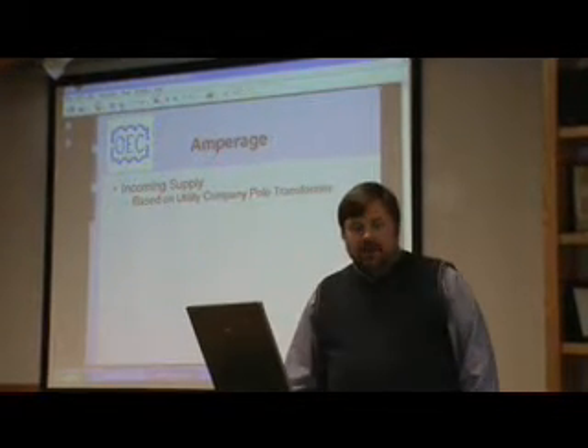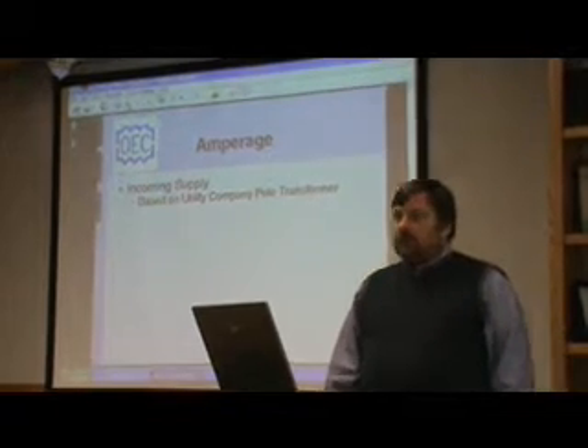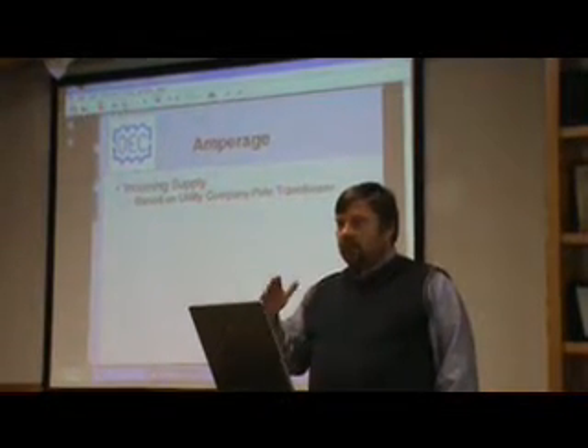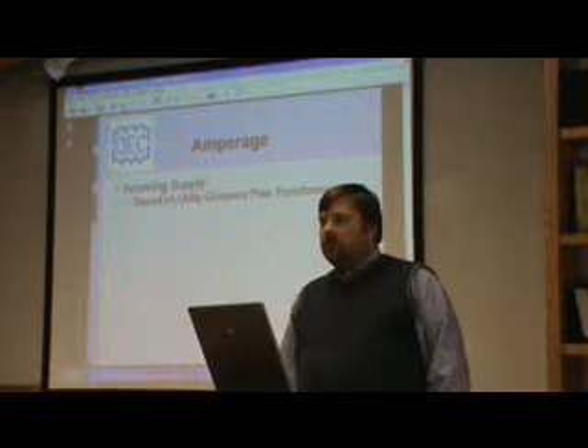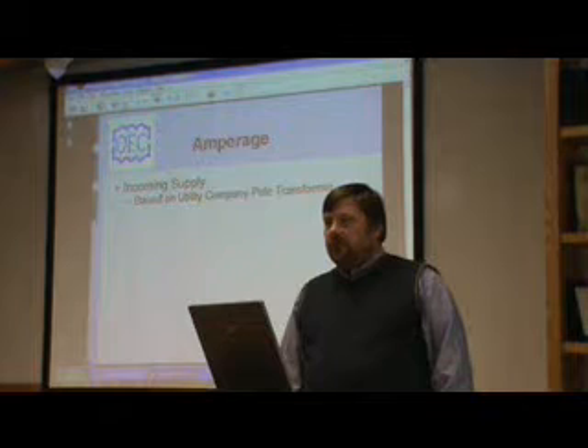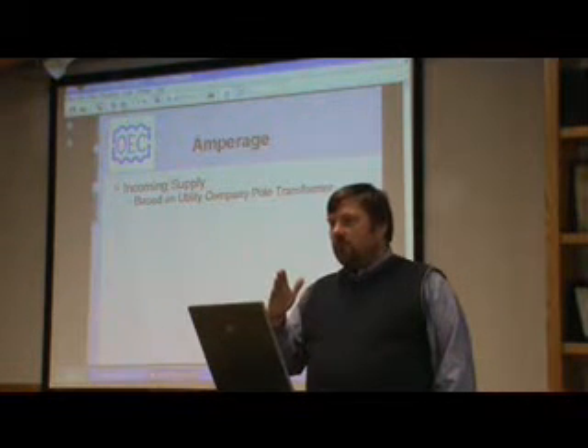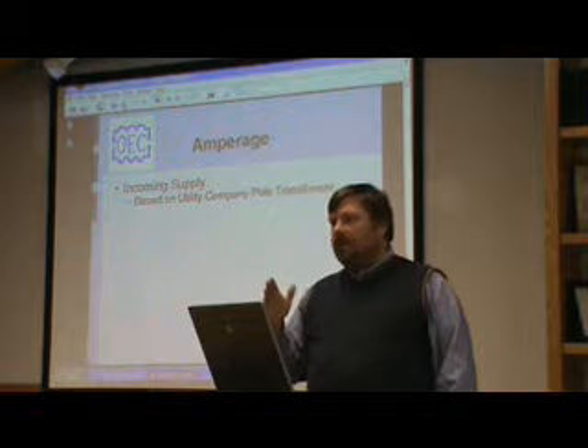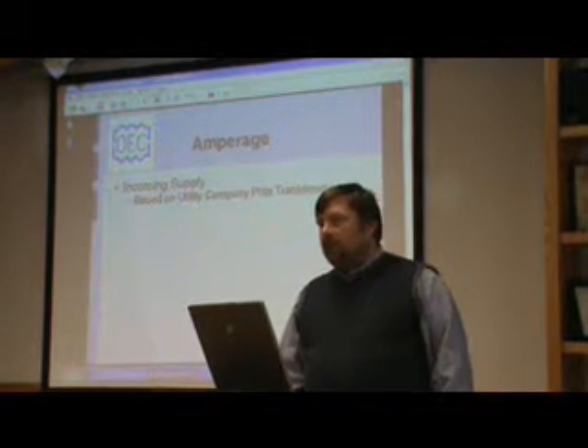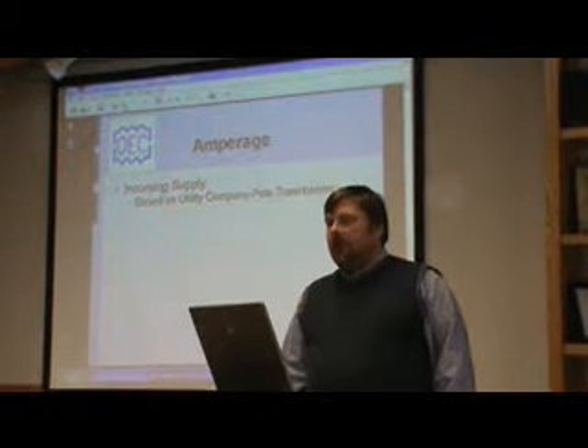What does it do to your equipment? To your equipment, it'll make your time clocks run a little bit slower. So if you've got an ETM, it's actually going to run a little bit slower on the generator than it would on the regular commercial power. When you run 60 cycle power versus 50 cycle power, the 50 cycle power will make your motor run a little bit warmer if it's not designed to be worked on 50 hertz. A lot of the motors and a lot of the stuff that we use in our control panels are rated for 50 or 60 hertz.